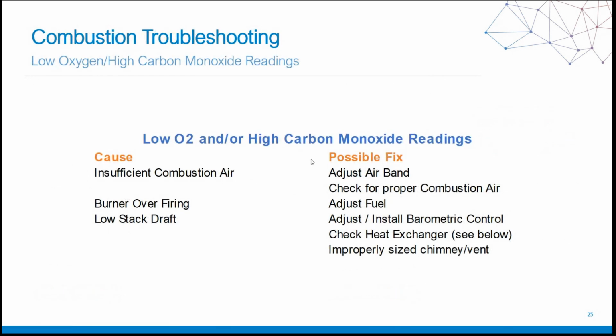Let's talk about a little bit of combustion troubleshooting here. Scenarios where we have low oxygen or high carbon monoxide readings. One of the issues could be insufficient combustion air. When we talk about an oil system, one of the things we want to adjust is the air band. And when we talk about insufficient combustion air, we also want to adjust gas pressure or fuel pressure. We want to make sure that we're using a proper size orifice and that we're not adjusting gas pressure too much, where we skew how that gas is actually being delivered into the system and for combustion.